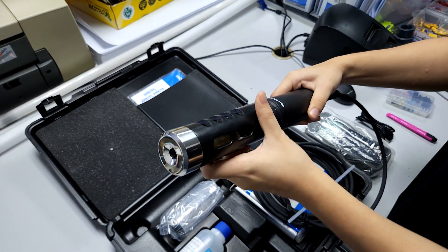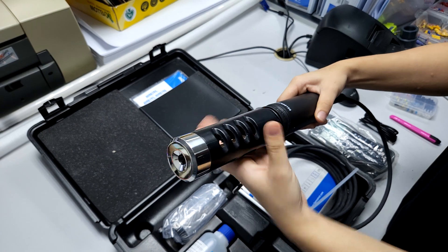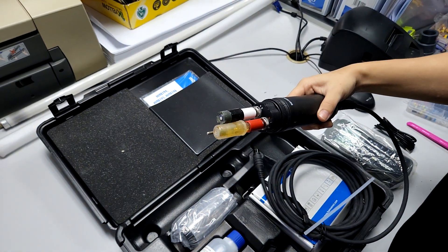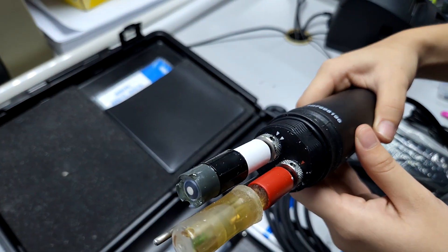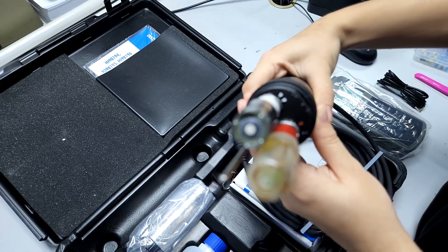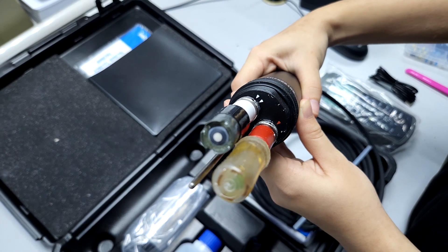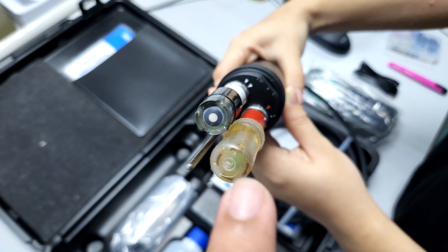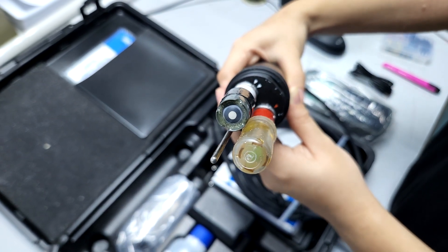What's different about this probe compared to our previous one is that it not only measures dissolved oxygen but also measures pH, ORP, and temperature — which is needed for the correction of the dissolved oxygen data. The black colour probe is actually the oxygen sensor, the one with the cap is the pH probe, and the one that looks like a steel rod is for temperature.